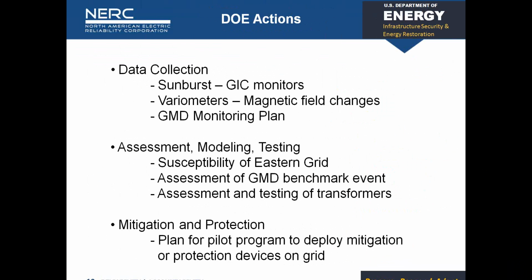So again, this doesn't protect, but it does let you know what the current is coming into your transformer in real time, and you can take measures to reduce the loading on the transformer if it's overheating, potentially try to drop the transformer because you don't want to have system damage.